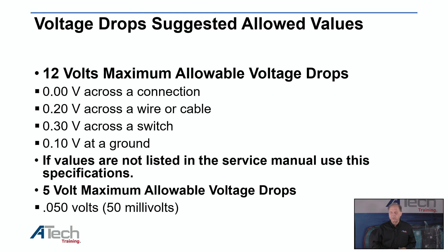A 5-volt circuit does not follow those guidelines. Normally we'll allow 50 millivolts on the ground side, or the voltage drop on a 5-volt circuit. Some people allow 70 millivolts. Whatever you want to look at is up to you, but I would always use the manufacturer specs if they're there. If not, use the generic specs.